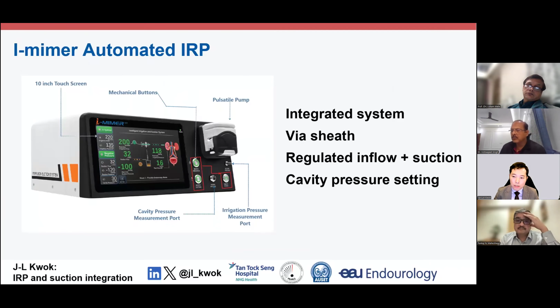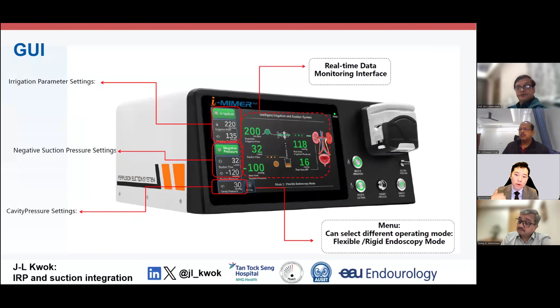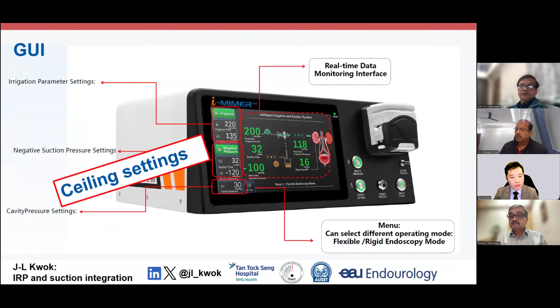It's an integrated system via the sheath with regulated inflow and suction with a cavity pressure setting. What do I mean by that? It means that you set irrigation settings, both in terms of mils per minute flow as well as the pressure, and you put a negative pressure setting, either by liters per minute or a suction pressure. But you also set a cavity pressure that you want the system to keep, and it auto-regulates based on the IRP that you're monitoring. So it's important to note that these are the ceiling settings that you're setting. The machine tries not to go above those settings regardless of irrigation, suction, or the cavity pressure.